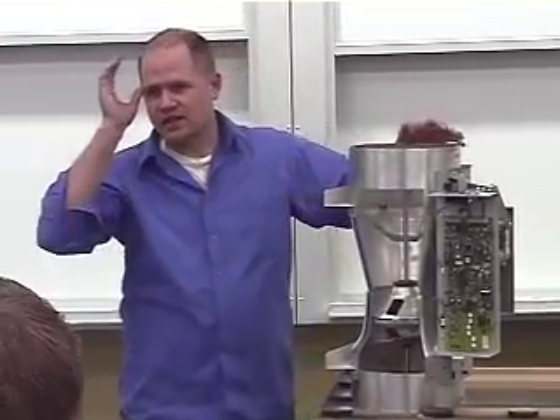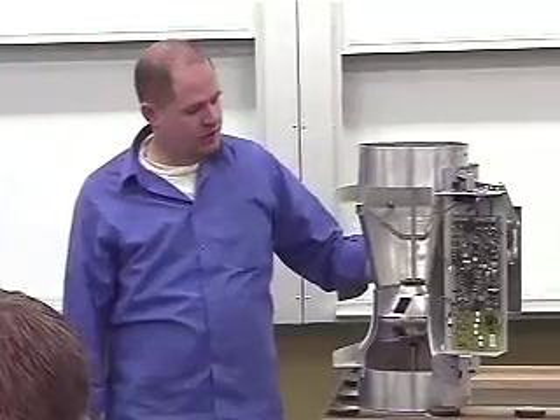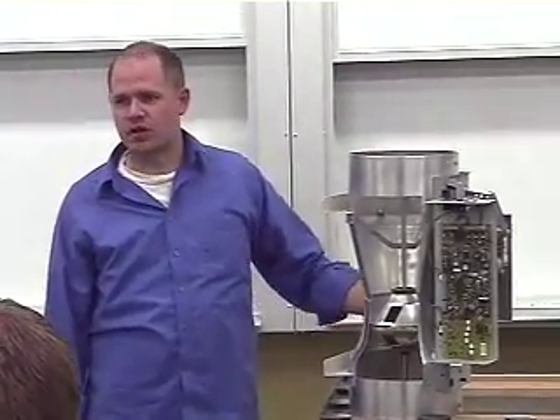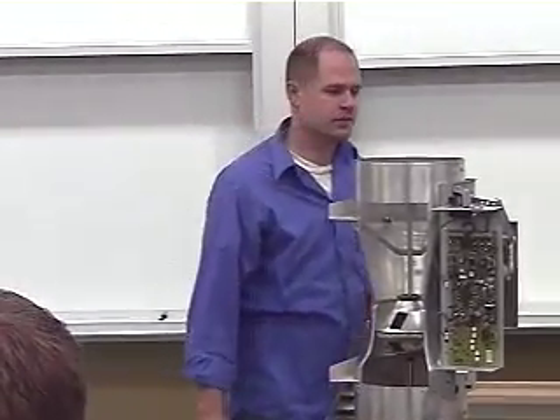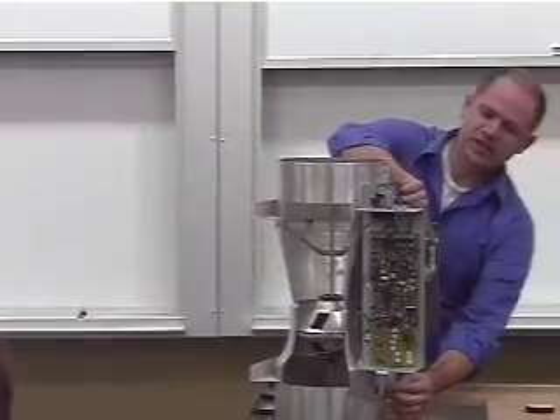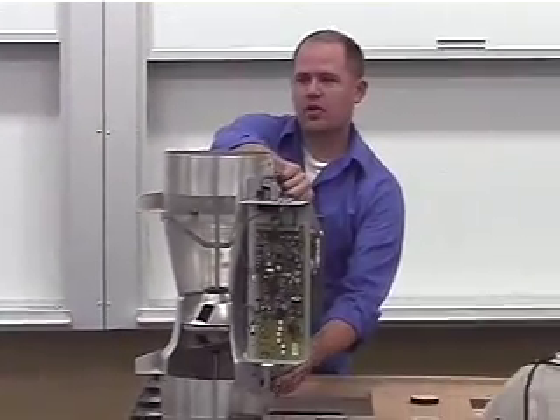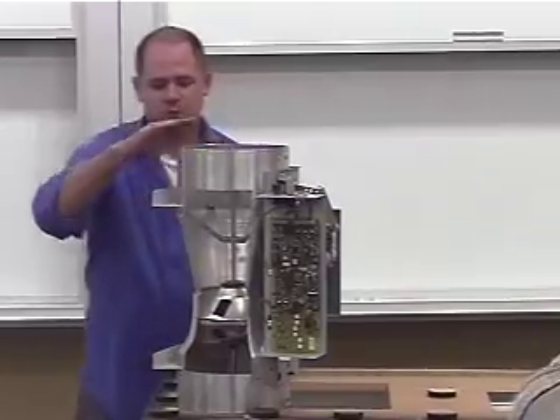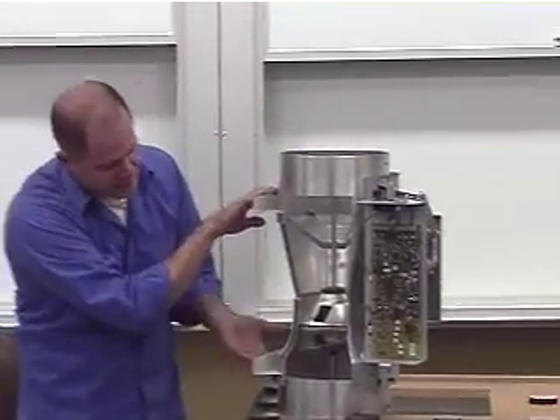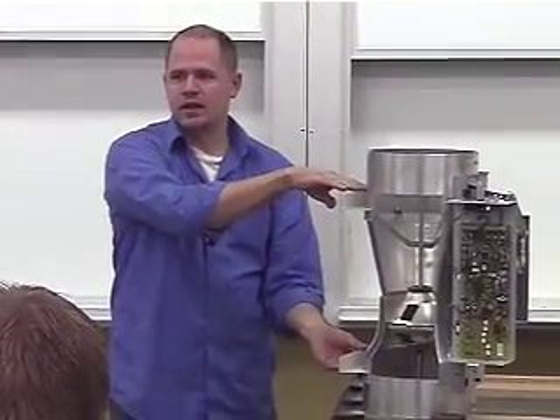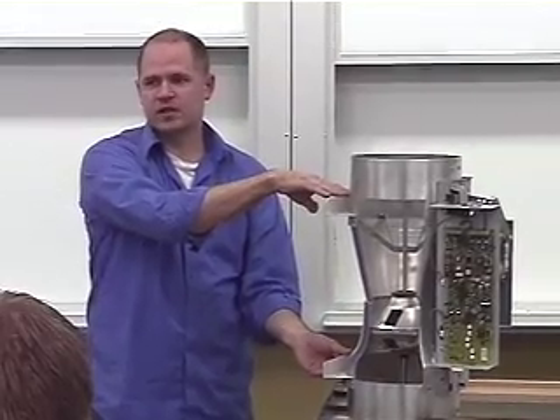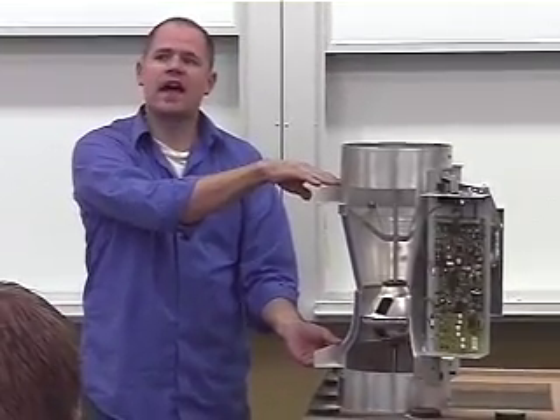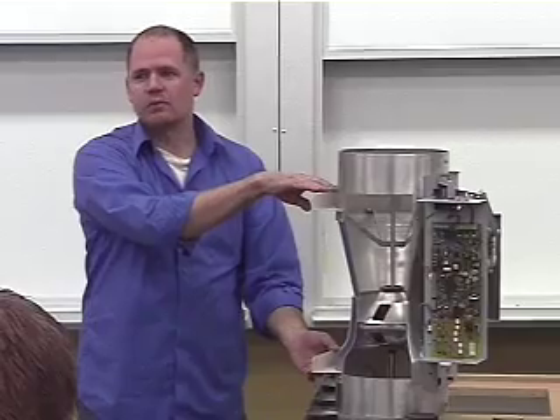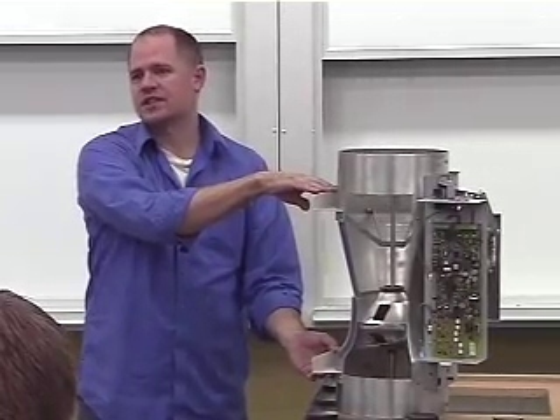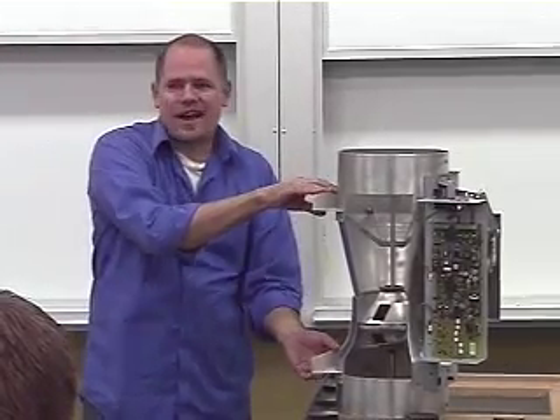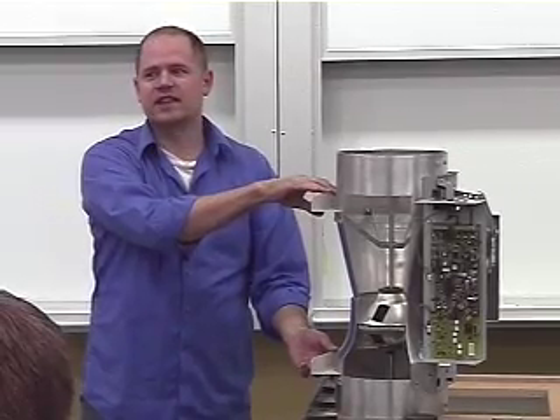The valves are designed specifically to have between 0.6 inches and 3 inches of air pressure across the valve. There are some ports on the top of these right here which can be measured. So your air pressure from the inlet side to the outlet side needs to be at least 0.6 inches in order to maintain the correct airflow. If it's not, then the valve goes into alarm and you'll see a flow alarm in your system indicating that I don't have my pressure drop, I can't guarantee that you're getting the airflow you want.